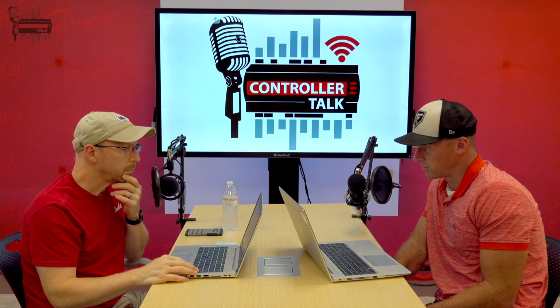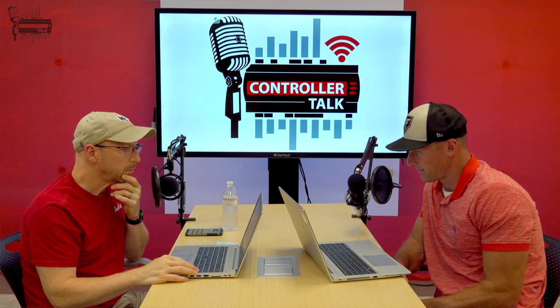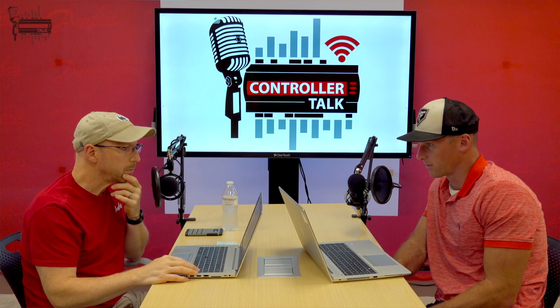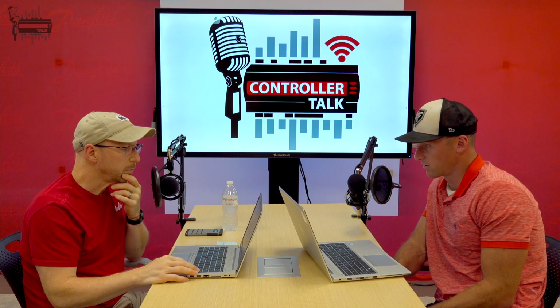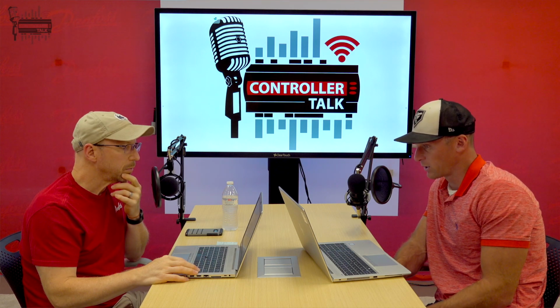Then we have a second display type, the newer of the two families, called the MMI GRS2, used for some other product types of ours too. This one gives a little more information and is a bit larger. It actually pulls in some data from the pack controller and can display that right on the front of the MMI GRS, so that's another option for somebody who wants a display. It uses the RJ11 port, right above the USB port on the pack controller, and this one is a little shorter, only up to 10 feet. But even 10 feet is probably fine, just from the pack controller to the front of the cabinet.